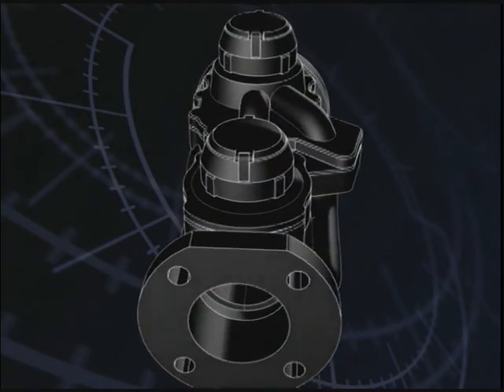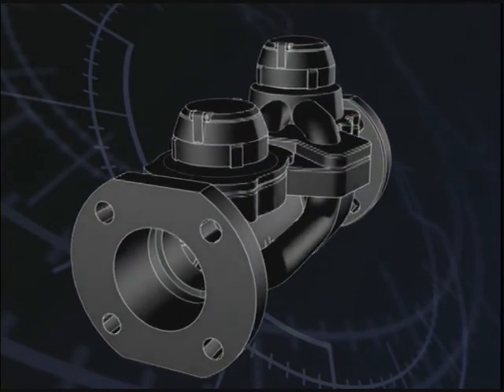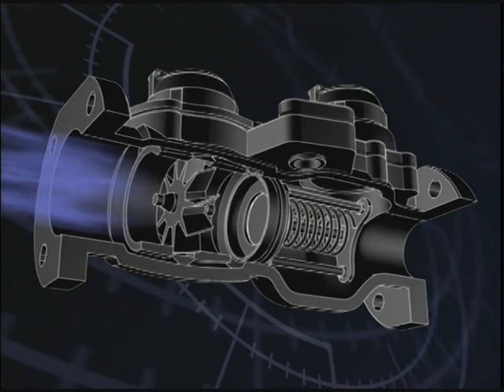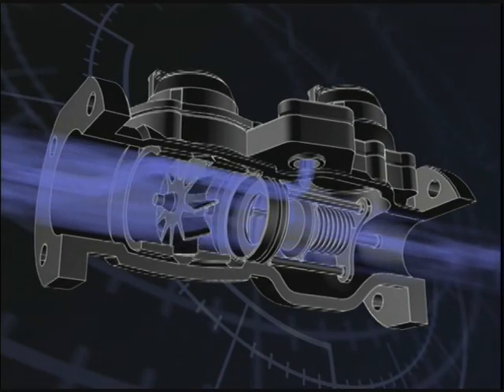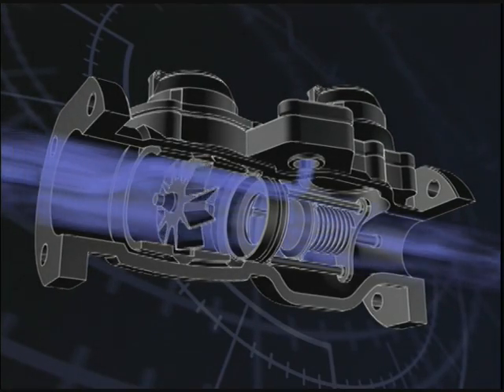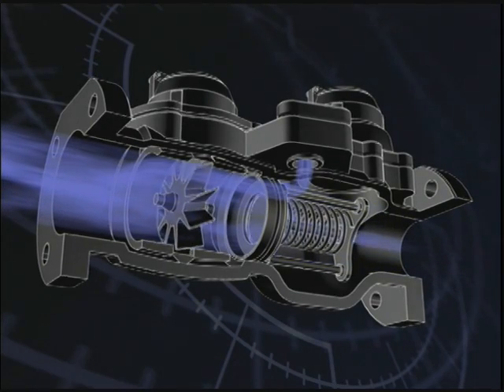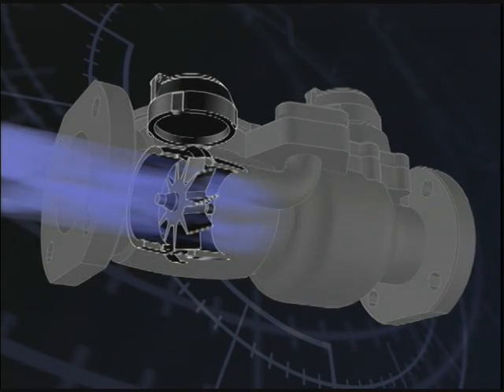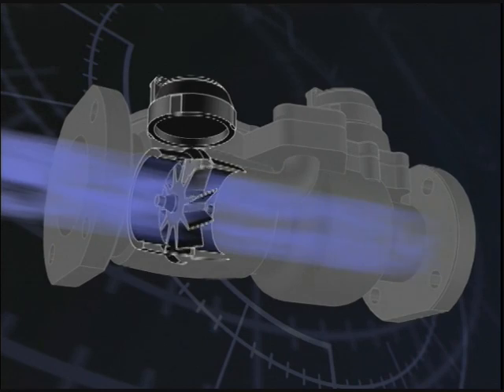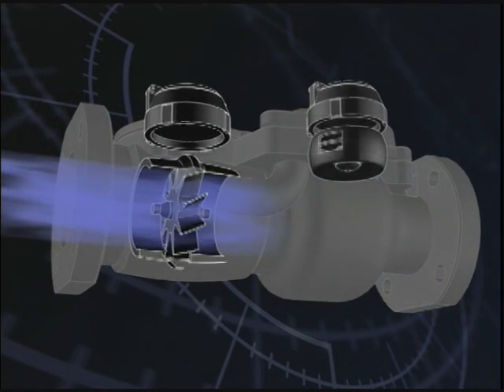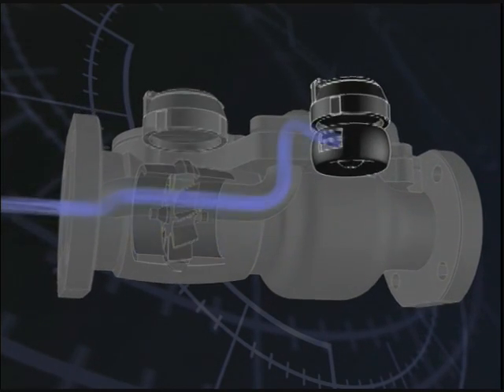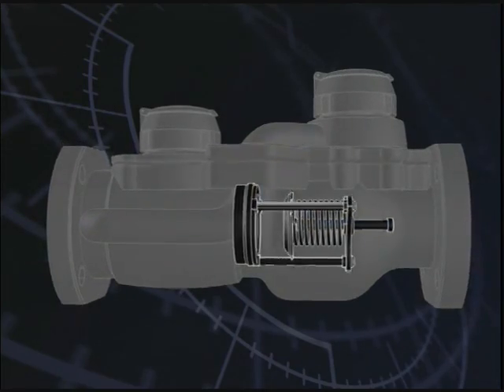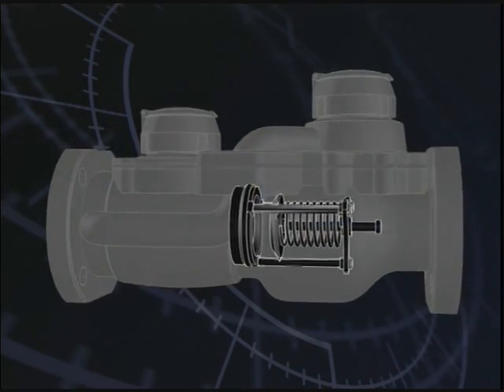Compound meters are often used for customers that have wide variations in flow rates and large quantities of water use. There may be times of the day when the water demand is very high, and other times when there is little or no use. A standard compound meter consists of three parts: a turbine meter, a residential type meter, and an automatic valve arrangement, all incorporated into one body.